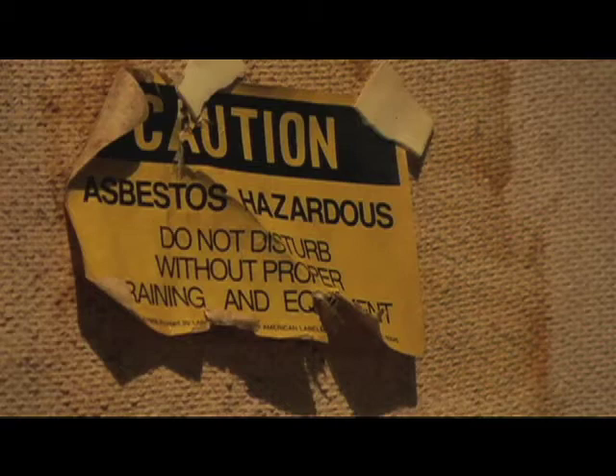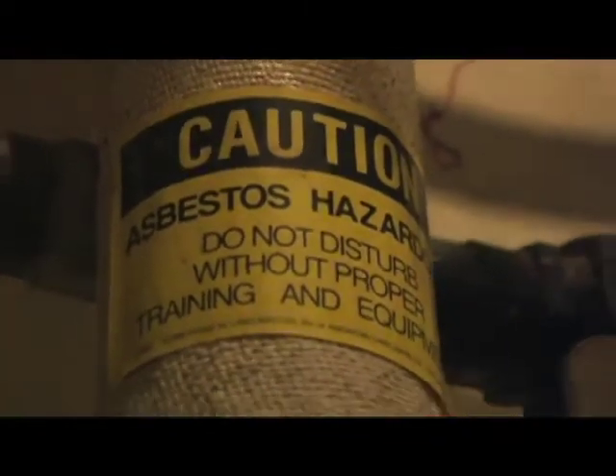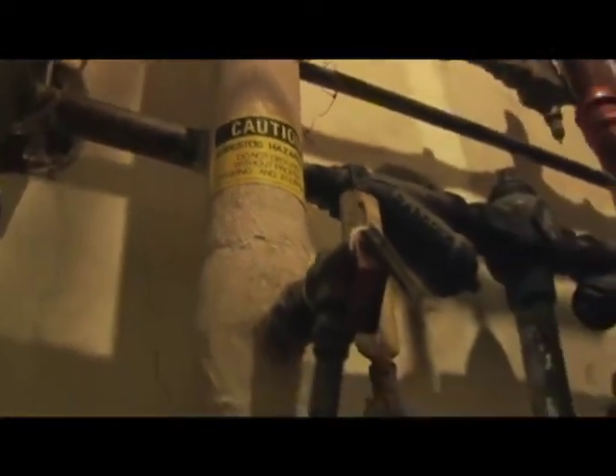One of the most significant needs is the original Fitzgibbon's boiler built in 1952. With its Nesbitt air handling units also originating from 1952, the system is in dire need of repair. The first thing that would need to be addressed is the asbestos related to the boiler. The entire boiler itself is encased in asbestos of the friable type. Friable asbestos describes any asbestos-containing material that, when dry, can easily crumble or pulverize to a powder by hand. Material that contains just 1% asbestos and is friable is considered to be regulated. This would apply to the pipes and the boiler in the boiler room.